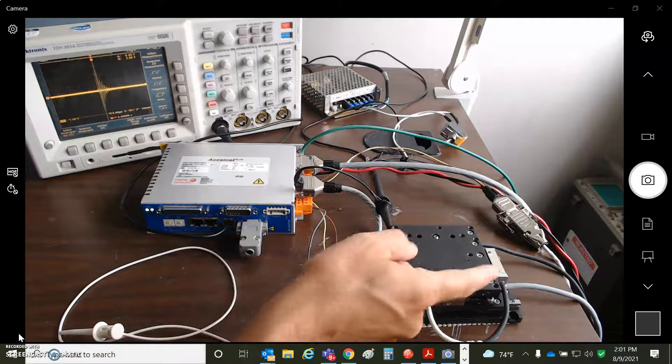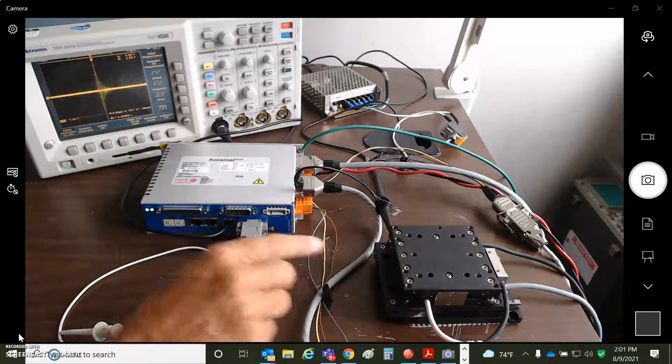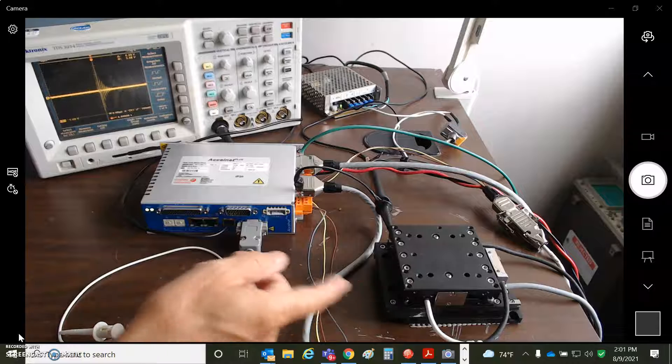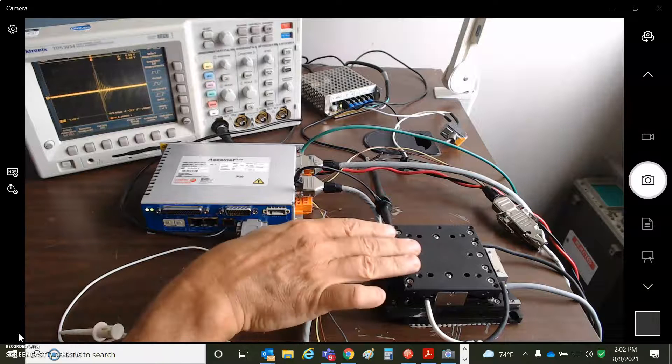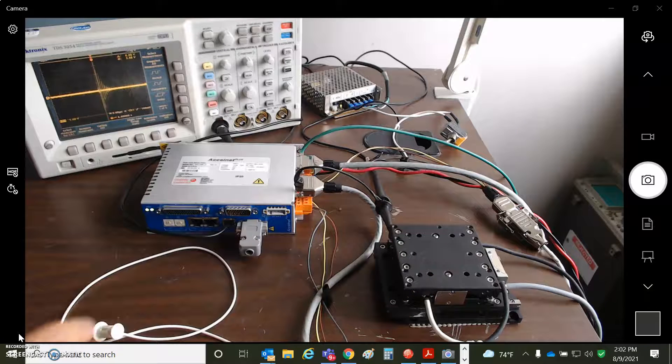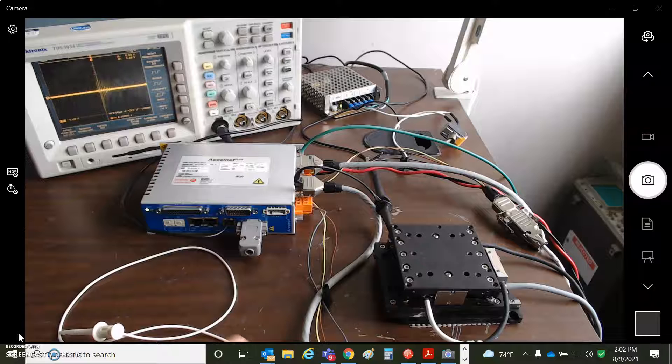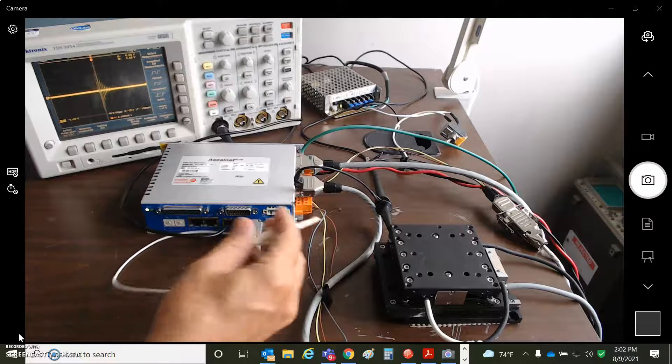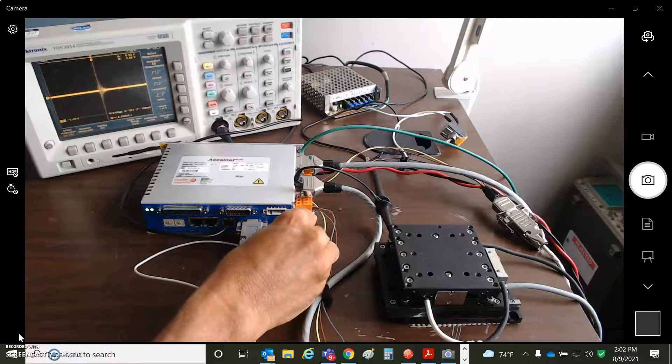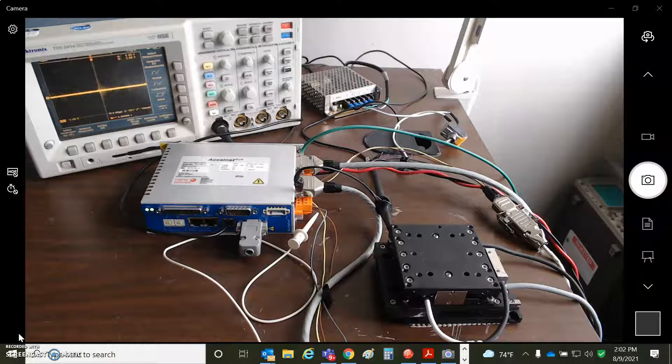Another Renishaw coming back. So what I noticed about this system was there wasn't a good grounding for the chassis, except for the shield of the motor cable. It didn't have a green wire, but they hooked up the shield to ground. And that helps a little bit.